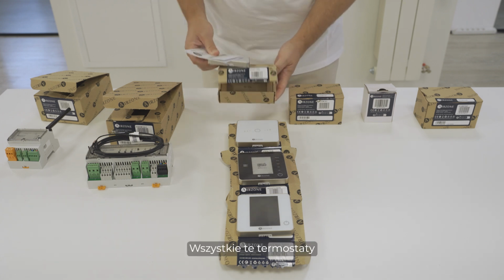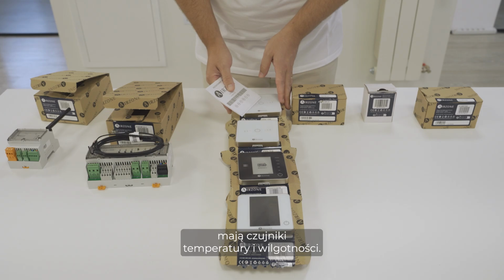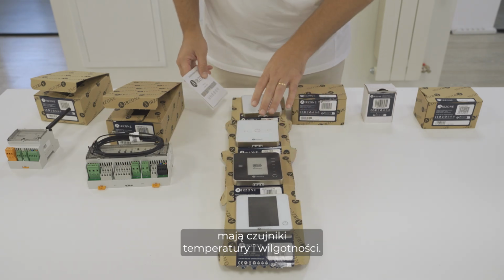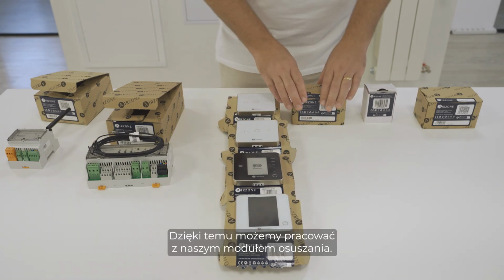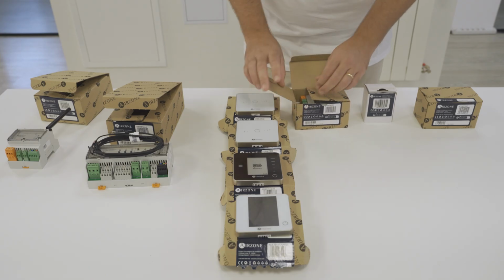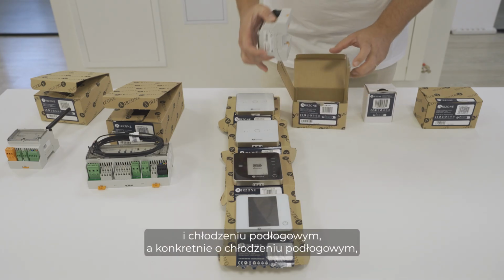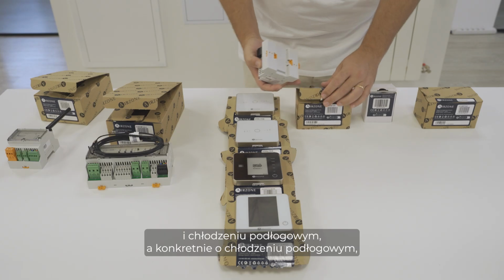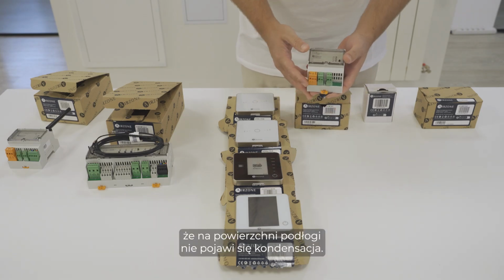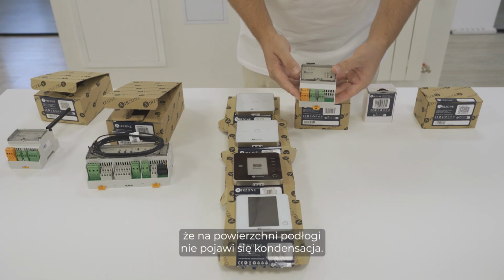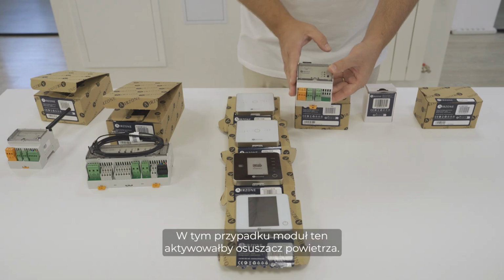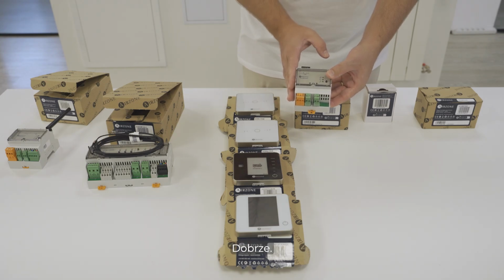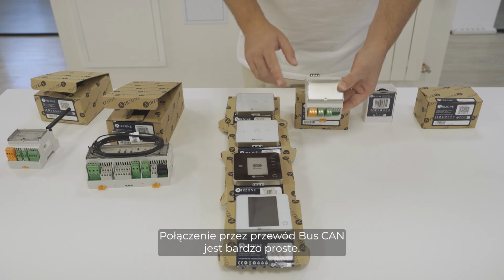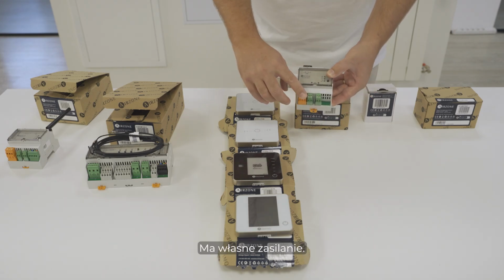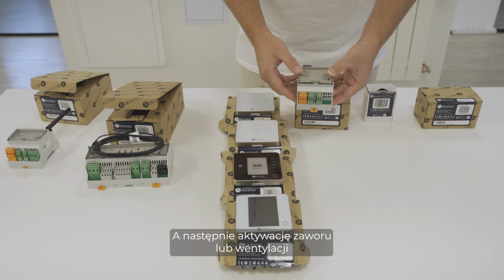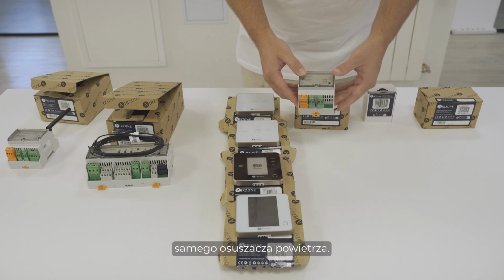These thermostats have all got temperature and humidity sensors. This allows us to be able to work with our dry module. When we're talking about underfloor heating and cooling, if we're talking about underfloor cooling, we need to make sure that we do not have any condensation build up on the floor surfaces. So in this case, this module would activate a dehumidifier, and it's a very simple connection through the bus CAN cable. It's got its own power source, and then the activation of the valve or ventilation of the dehumidifier itself.